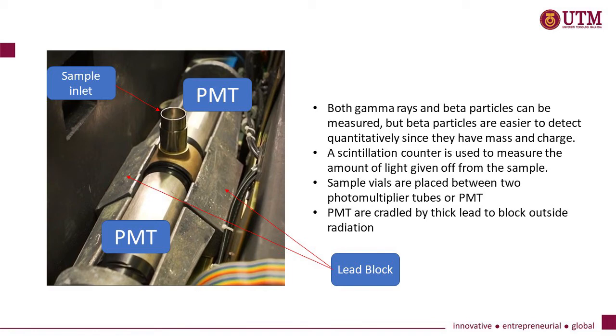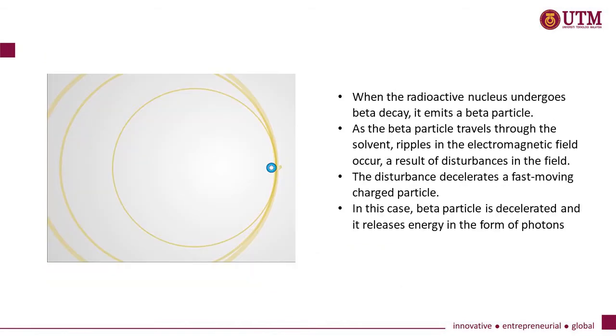Sample vials are placed between two photomultiplier tubes, or PMTs, and cradled by a thick lead shield to block outside radiation. When the radioactive nucleus undergoes beta decay, it emits a beta particle. As the beta particle travels through the solvent, disturbance in the electromagnetic field occurs.